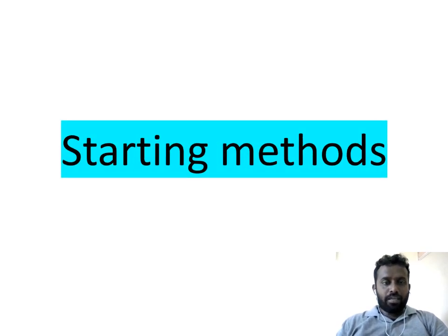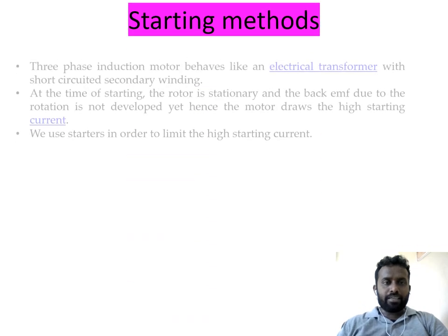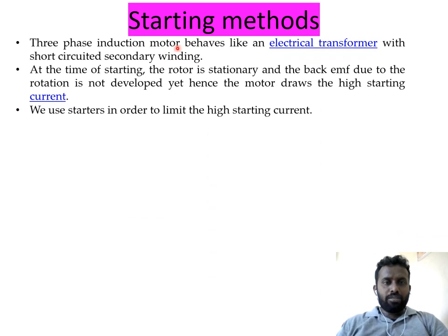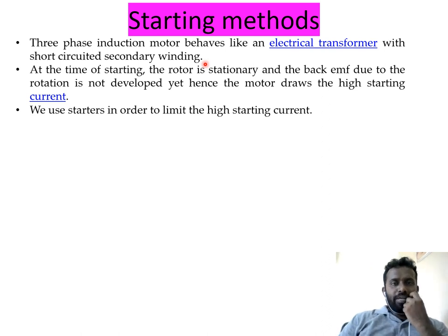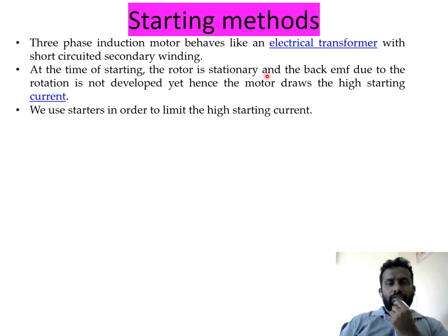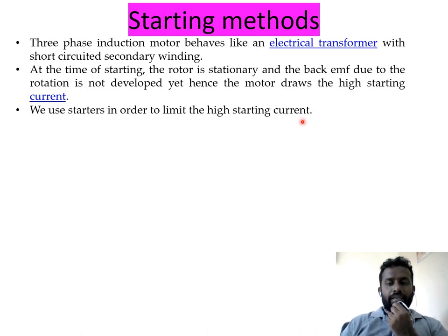Now, starting methods. Why do we need a starter? The three-phase induction motor behaves like an electrical transformer with a short-circuited secondary winding. At the time of starting, the rotor is stationary and back EMF due to rotation is not developed yet. Hence, the motor draws a high starting current. We use starters in order to limit this high starting current.